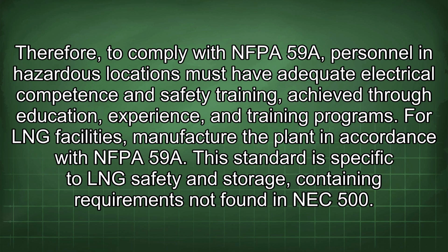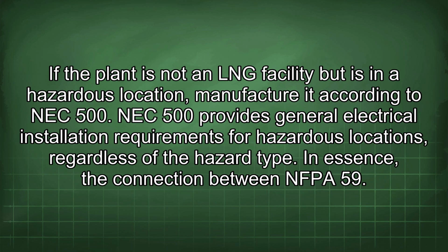For LNG facilities, manufacture the plant in accordance with NFPA 59A. This standard is specific to LNG safety and storage, containing requirements not found in NEC 500. If the plant is not an LNG facility but is in a hazardous location, manufacture it according to NEC 500. NEC 500 provides general electrical installation requirements for hazardous locations, regardless of the hazard type.